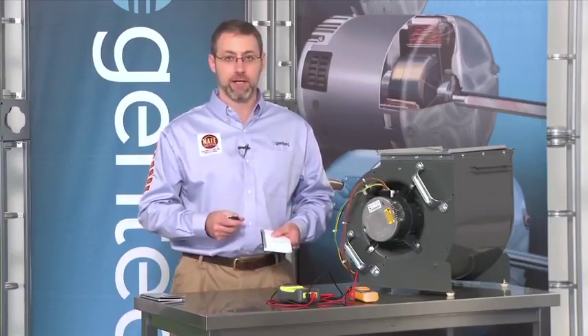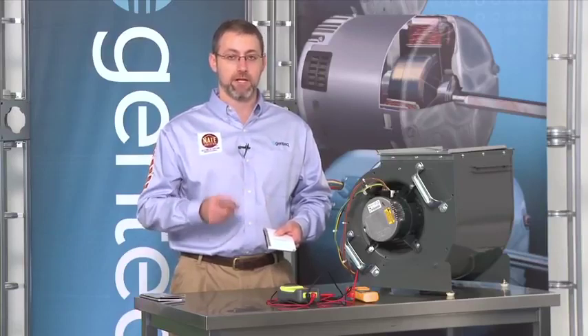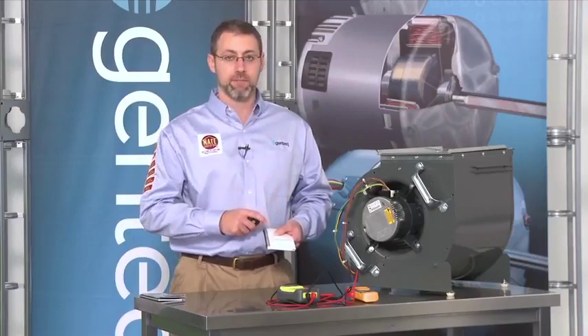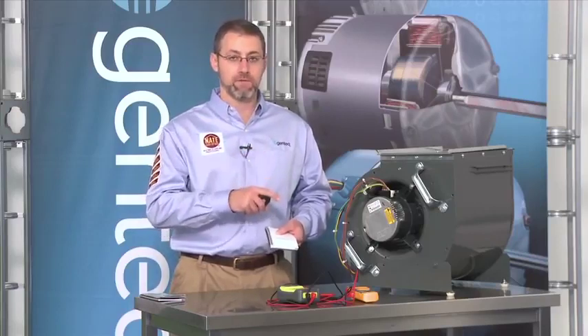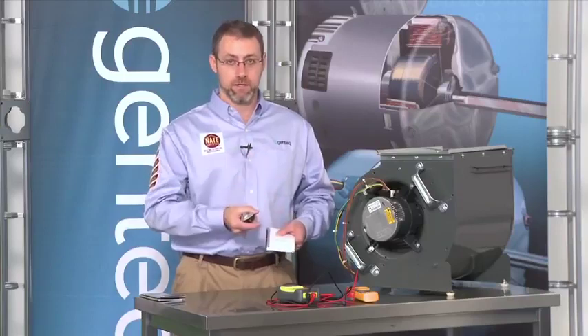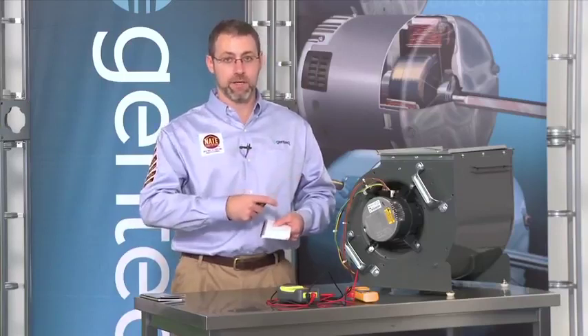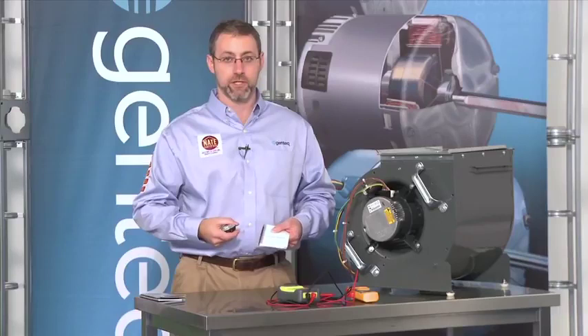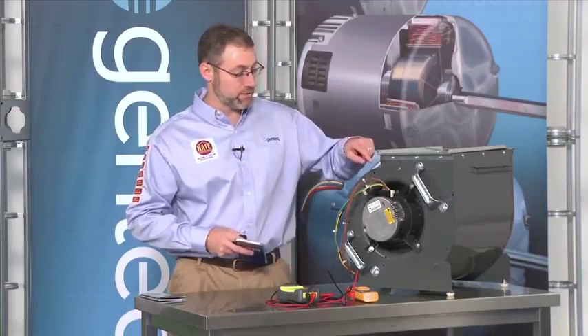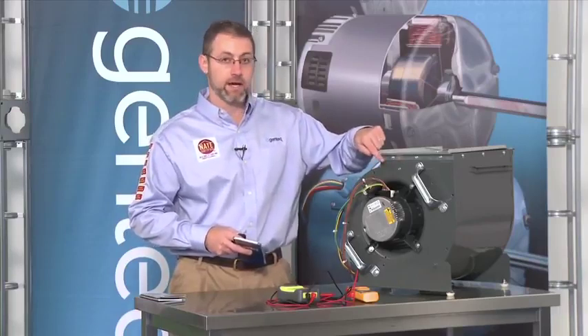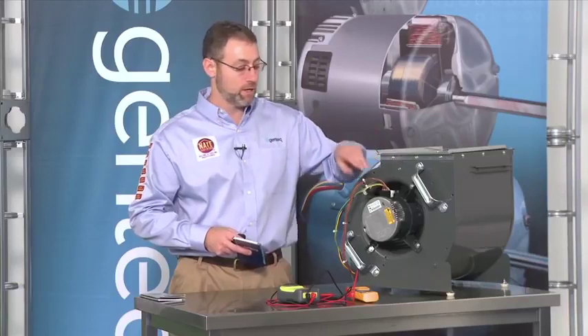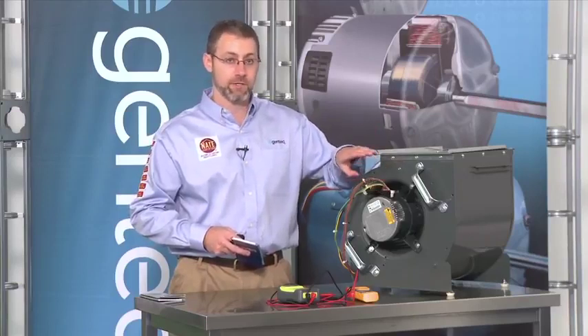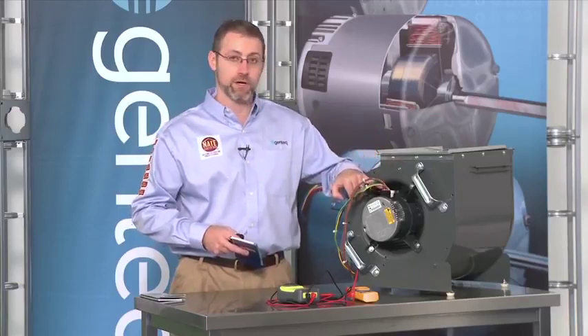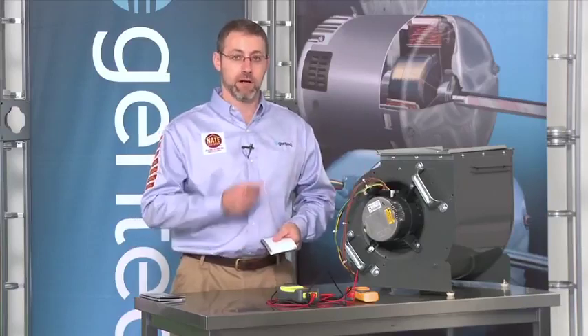You can check that power anytime. The low voltage will only show up when there's a thermostat demand and the OEM circuit board has timed out any delays that might be in the board. So to check the low voltage, we will need to give a thermostat demand, wait for that demand to time out, and then check the low voltage at the motor. If the manufacturer uses a low voltage and a high voltage plug at the motor, we will have to have both plugs out to check our low voltage to our common pin, which is in our upper plug.